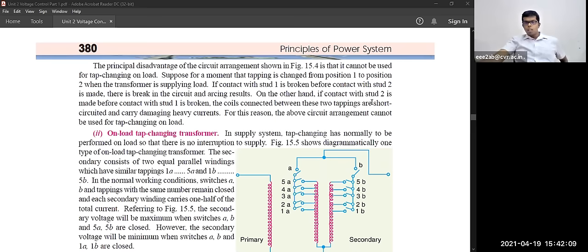On the other hand, if the contact with stud 2 is made before the contact with stud 1 is broken, sometimes this contact also will be broken. Then the coils connected between these two tappings get short circuited and carry heavy damaging currents. So due to this short circuit between the two studs, it will also carry heavy currents.